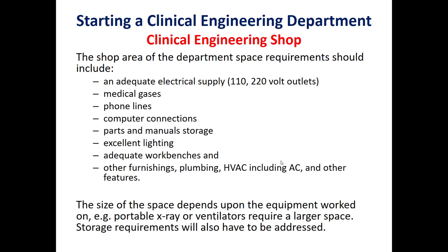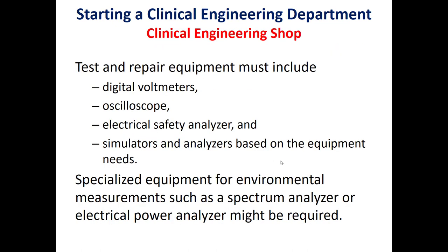Regarding test equipment in the clinical engineering shop, it should include a digital voltmeter, an oscilloscope, an electrical safety analyzer, and simulators and analyzers based on equipment needs. Additional testing equipment may include environmental measurement tools for measuring power frequency and so on, such as a spectrum analyzer and electrical power analyzer.